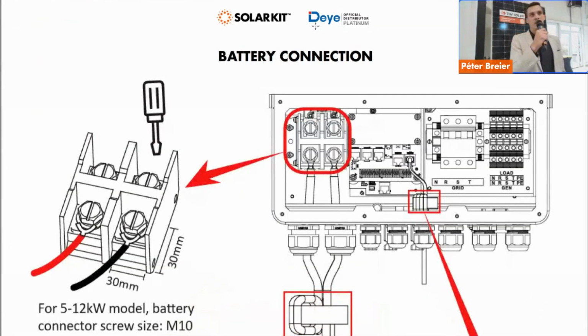After that, we move on to the battery input, because one of the very big advantages of the Deye inverter is the battery compatibility and the price of the batteries, of course. So basically, these are pictures from the user manual, and you need to remove the bottom cover of the inverter to see that part. This is where you make all the connections, and this is what you need to open if you are an installer. The top part of the inverter can also be removed, but it's only for the service centers of their products. So if you are an installer, you do not need to remove that, and you are not allowed to remove it without losing the warranty. So you only need to use the bottom part.